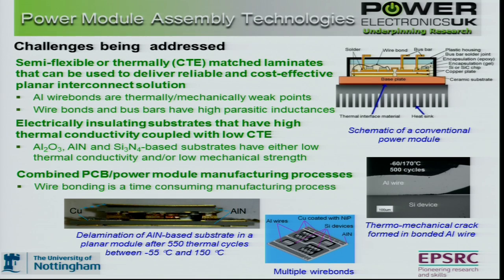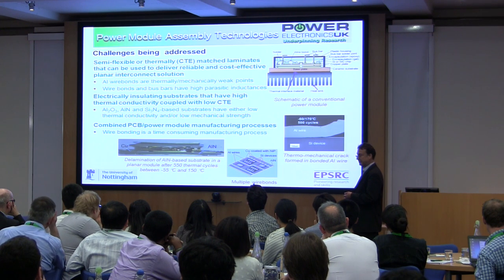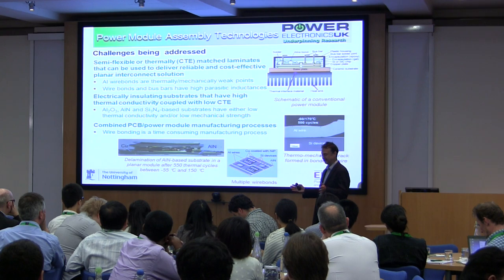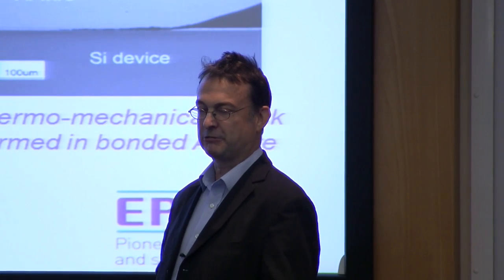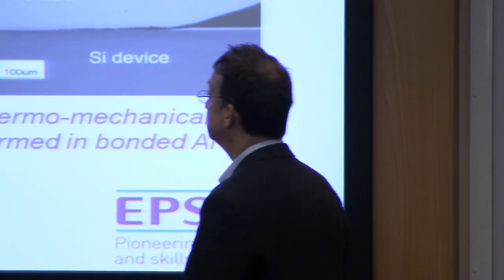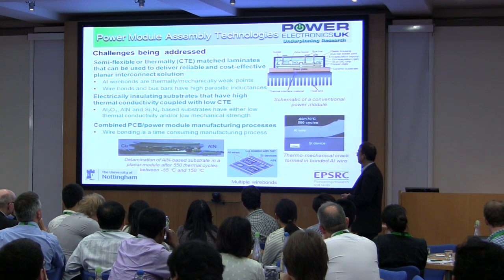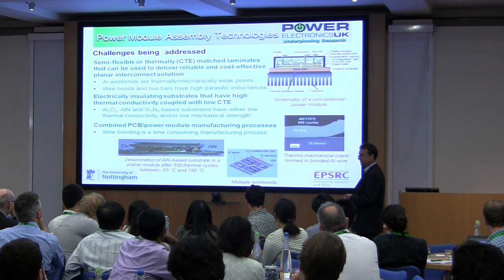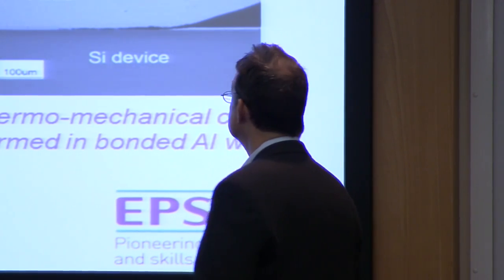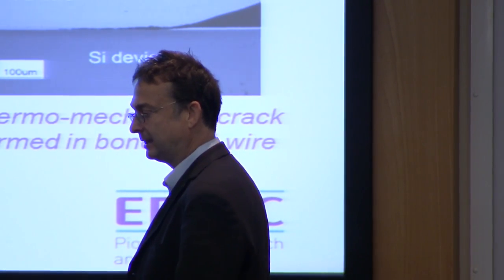This slide says wire bonding is a bad thing — let's get rid of it. So let's look at new technologies to eliminate wire bonding through various flexible packaging technologies. Another bad thing is the incompatibility of the thermal expansion of the actual power semiconductor devices and the substrates and packages at which they're mounted. We have problems where they have different thermal coefficients — CTEs — and also some of the established substrates, although they perform very well electrically, could perform better thermally and mechanically.